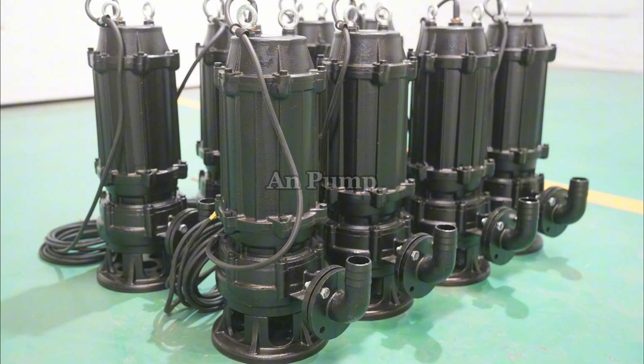For sewage applications, submersible pumps often use vortex impellers, single-channel impellers, or semi-open chopper impellers that can pass fibrous solids and rags without clogging. These pumps are used in municipal wastewater collection, groundwater extraction and borehole pumping, construction site dewatering, stormwater management, aquaculture, mine dewatering, and residential deep well pumps. Performance ranges vary widely. Borehole pumps can handle 0.1 to over 500 cubic meters per hour with heads over 600 meters. Sewage pumps can go from 5 to over 20,000 cubic meters per hour with heads over 100 meters.